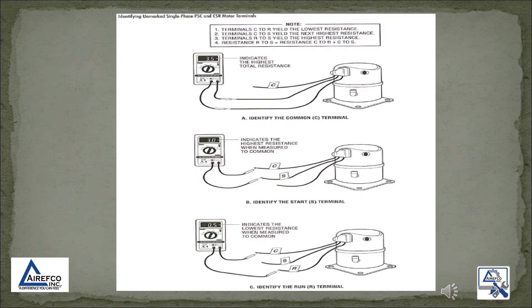In the procedures manual it shows you taking your ohmmeter and taking resistance readings on the leads of the compressor. The highest total resistance indicates the start and run windings, and so your third wire would be your common terminal. The next highest resistance shows your start winding, and then the lowest resistance when measured to common indicates your run terminal.